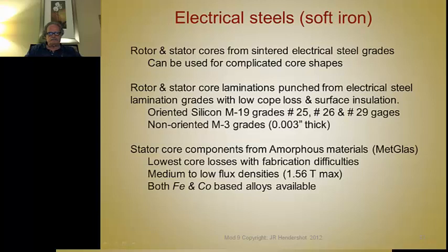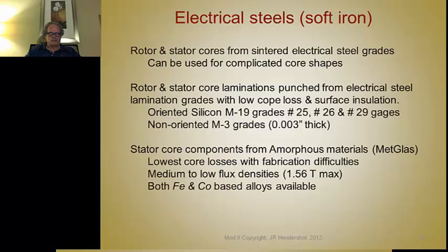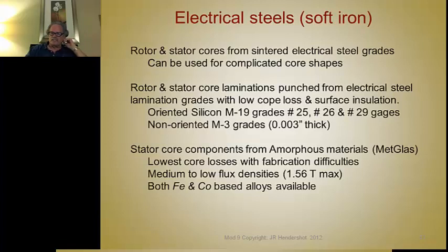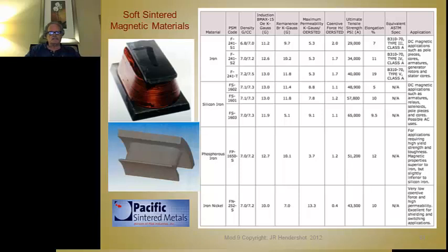There's also a class of amorphous materials with the trade name Metglas. These have very low core losses but their maximum flux density is quite low — they run around 1.5 tesla instead of 2.0 to 2.1 tesla like the other grades.